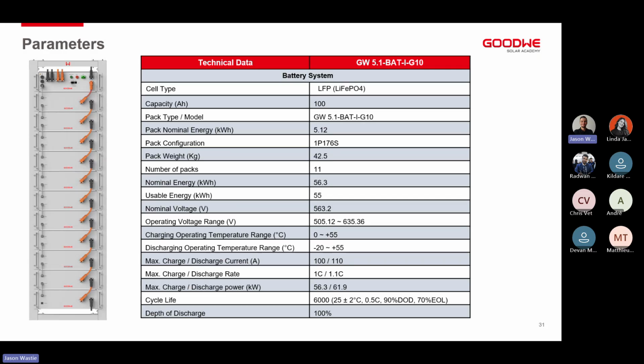This battery and the previous battery that we mentioned both have black start functionality, meaning that we can black start the system, start the inverters up using just the batteries and get an output. We don't need PV, we don't need the grid in order to start the system up, start the batteries up. There's no AC power requirement from the batteries as well. They can power up and output from just DC power. There is no AC power connection required in order to keep the PDU alive or keep it connected. We don't need a UPS to keep it working or anything like that. We just connect the batteries together, turn the battery on, and off we go.